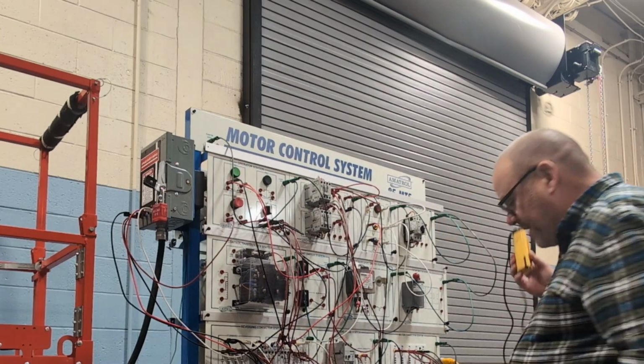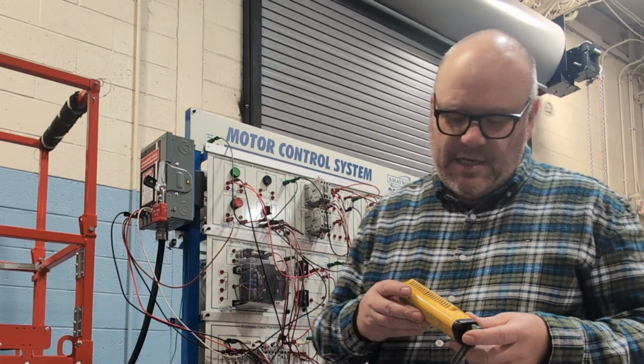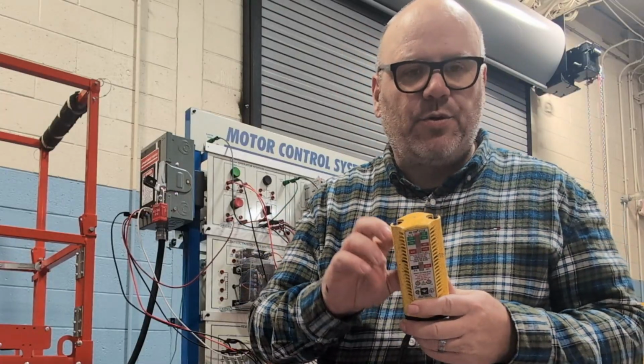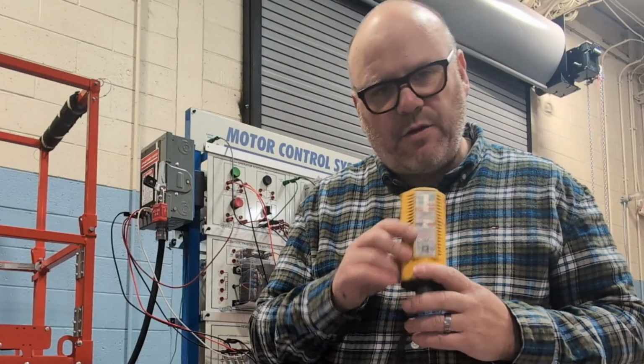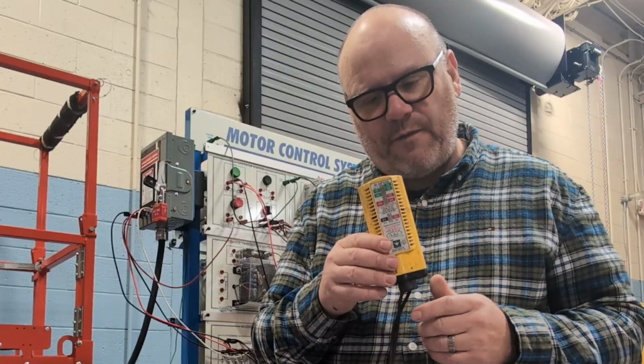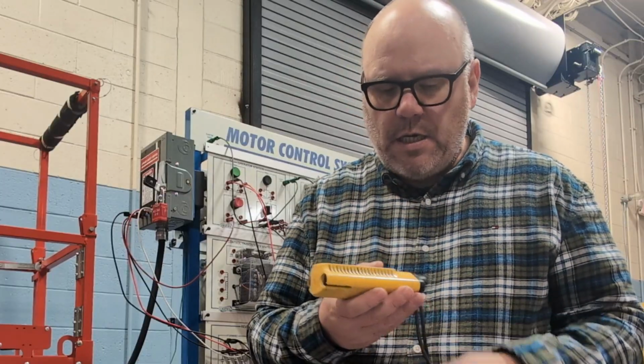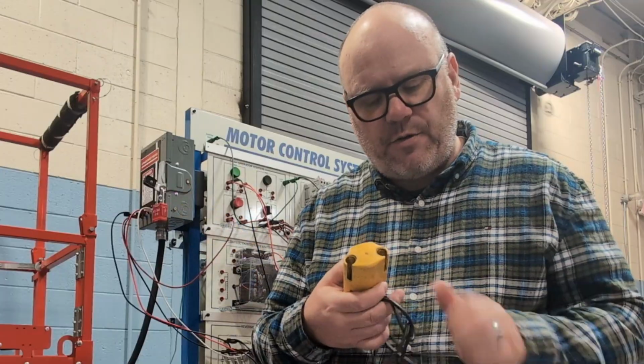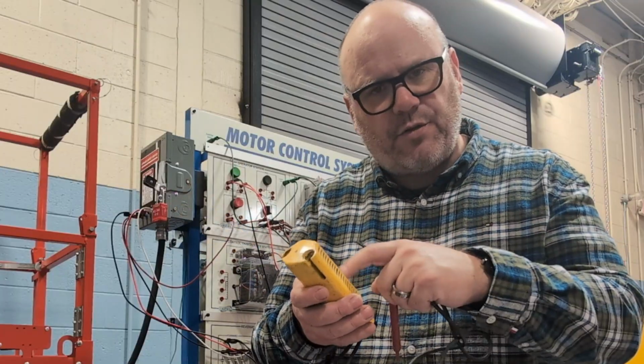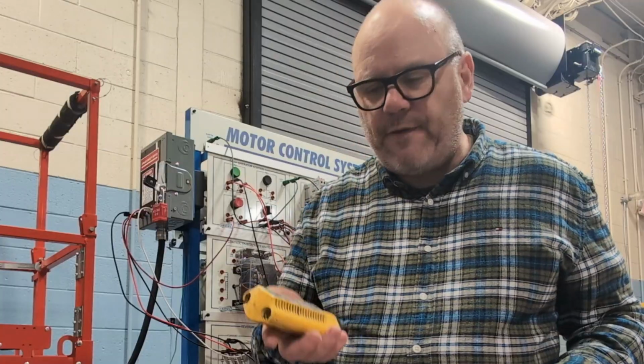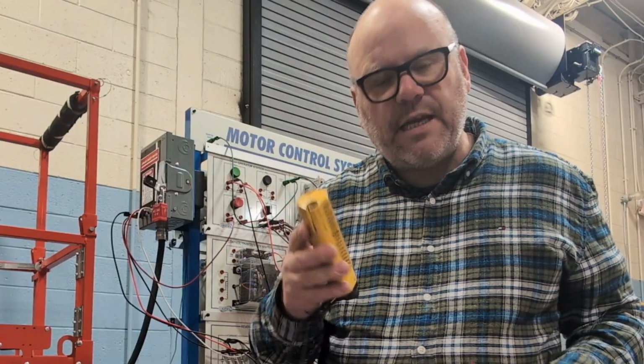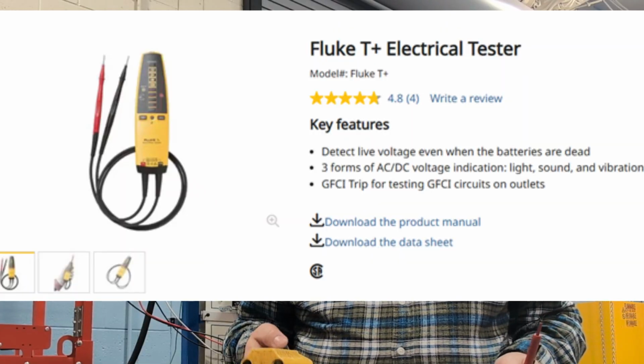Now I'm going to show you something that if you have, throw out. We call this a wiggy. It has a solenoid inside. This literally blew up in my face with 120 volts. Luckily I didn't get hurt. It uses a solenoid, so you attach the voltage to it, it runs the solenoid, and again, it blew up in my face. So I would recommend not having this. They have newer ones with electronics instead, that's the one I would recommend instead of this one. I would only use it for verifying voltage, that is it, I don't use it for anything else.